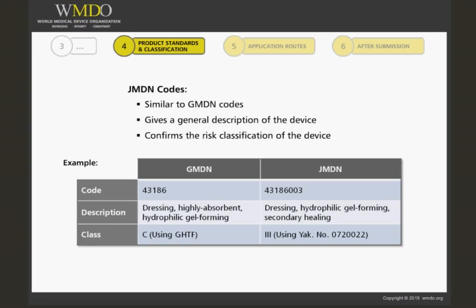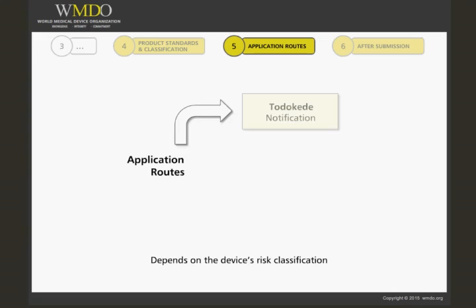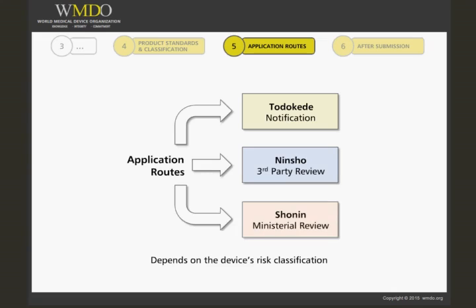Do you see the theme here? It is imperative that the Japanese MAH is involved as much as possible. Basically, depending on your device's risk classification, there are several routes you can take: the TODOKEDE route, or notification; the NINSHO route, or third-party review; or the SHONIN, which is the ministerial review by the PMDA.